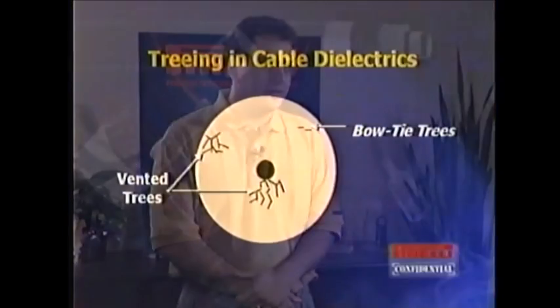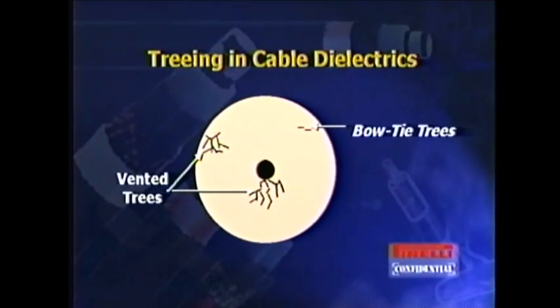What we want to get across is that a cable tree or a water tree is referred to as a degradation of the insulation due to voltage stress and water inside the insulating material. There are two different types of trees that are commonly referred to. One is called the bow tie tree, which usually starts somewhere in the insulating material itself and is usually initiated from some type of a contaminant or something in the extrusion process that just wasn't right.